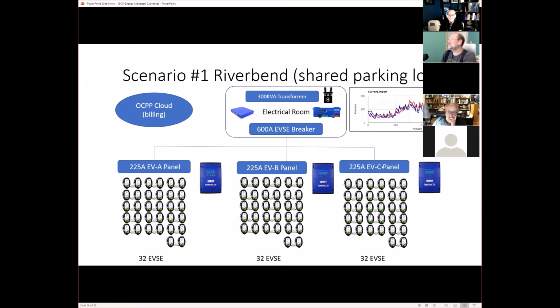So we set up 3 panels. The first panel, which was the one that we've actually deployed, is called EVC, and it has a 225 amp breaker for the main breaker on that panel. There's room for 32 EVSEs, and we have our Dent meter measuring all the consumption. So if Riverbend wants to charge by the kilowatt hour, everything is there to make it revenue grade. They would just need to get the meter sealed and certified, and they would be billing by the kilowatt hour, which everyone keeps saying can't be done. It's not possible.